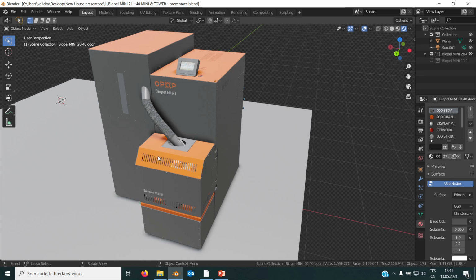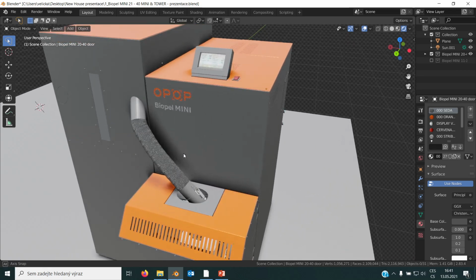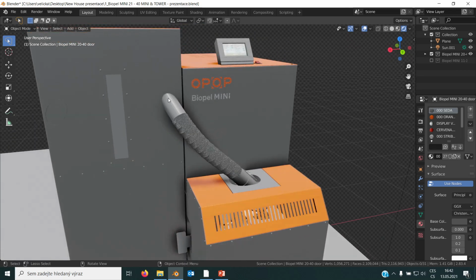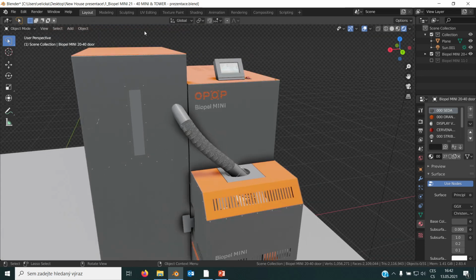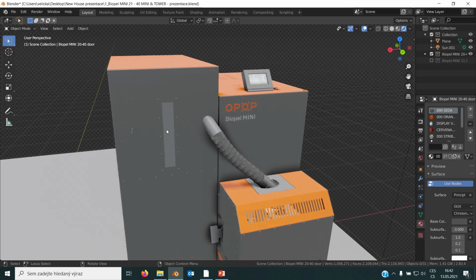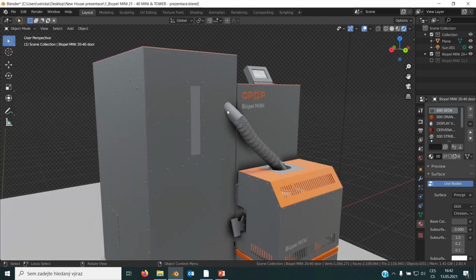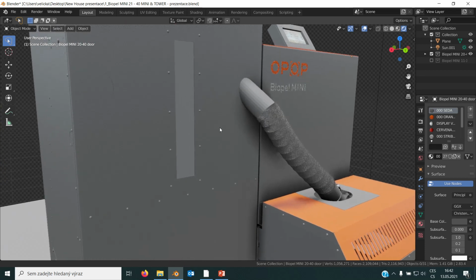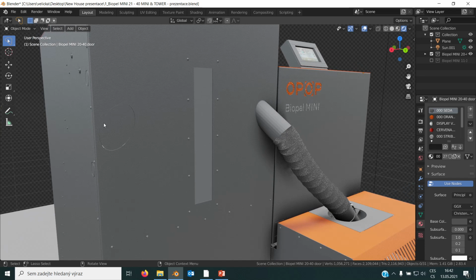Now about the feeder installation and cable installation. When you buy the boiler, the feeder itself is not installed inside the pellet hopper. It is placed inside the hopper, but you will select the position. You will choose the position where the feeder outlet should be. If you see closely, there are again openings covered by plate here and here. And this is again for the outlet of the feeder.